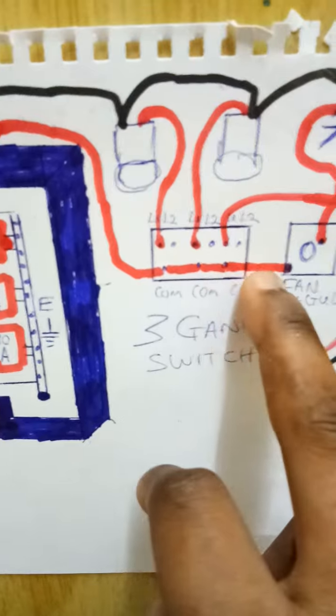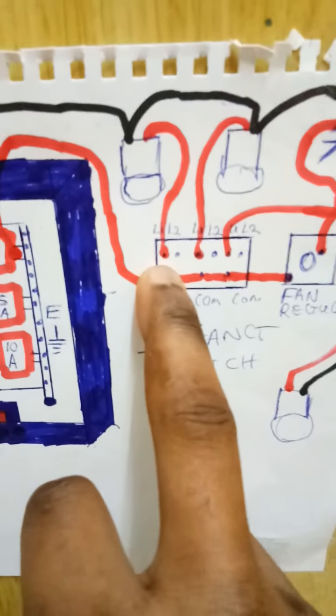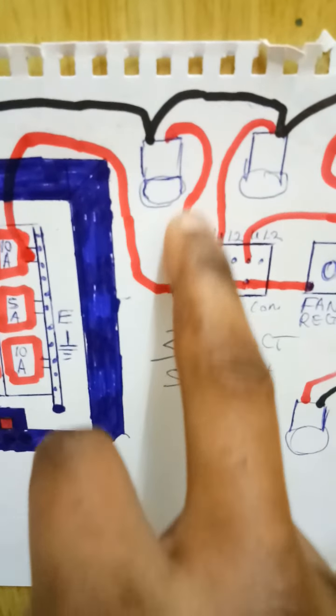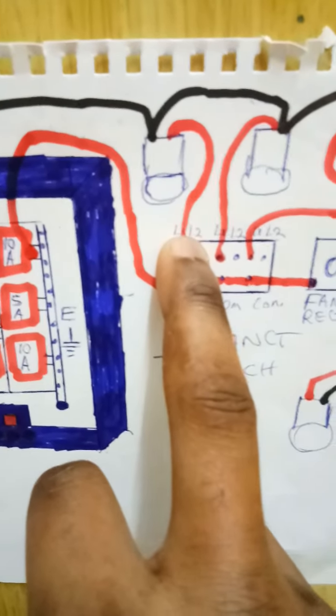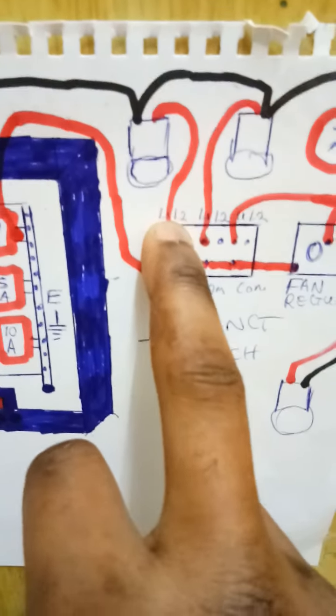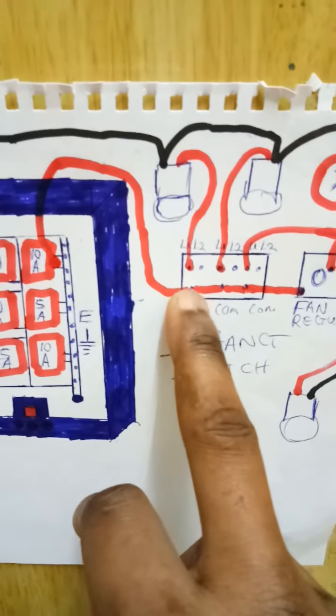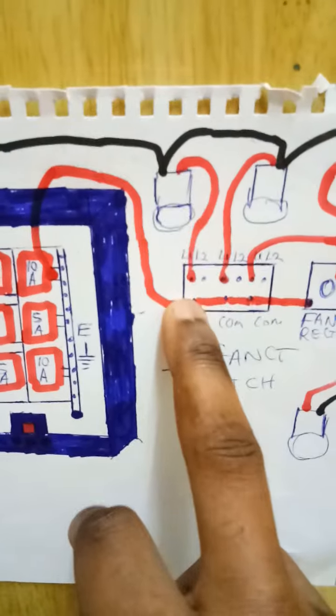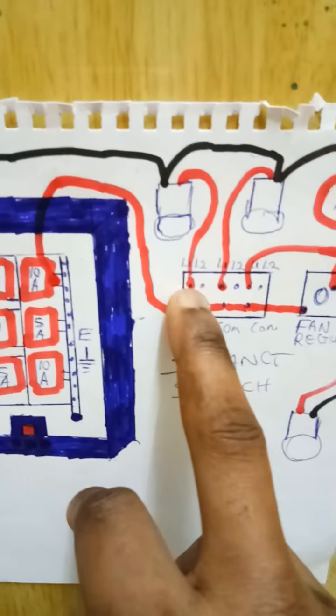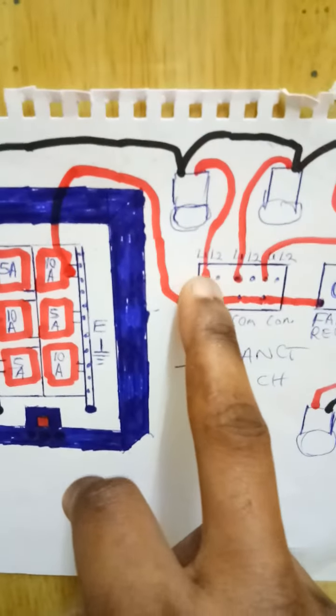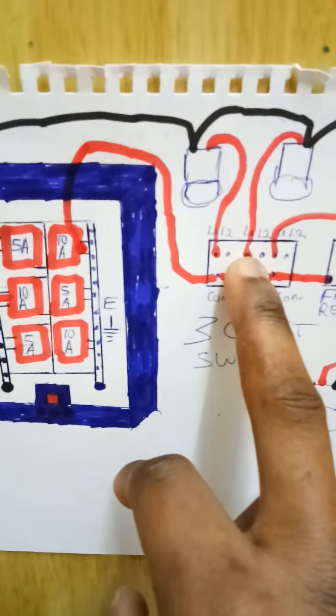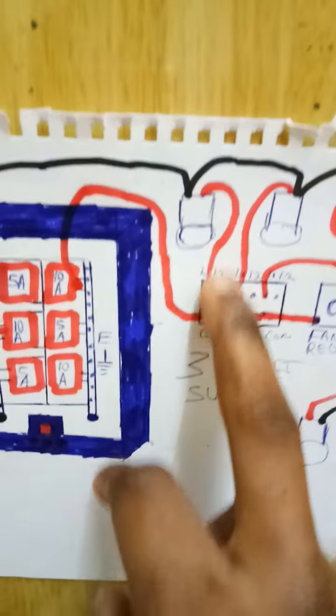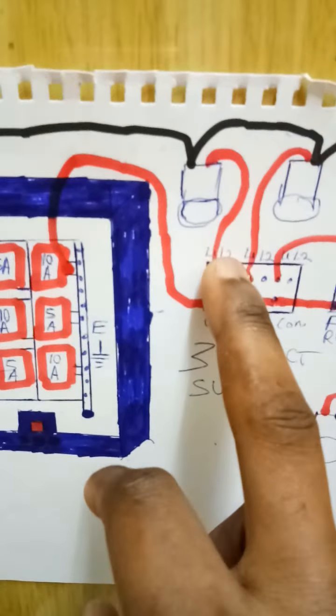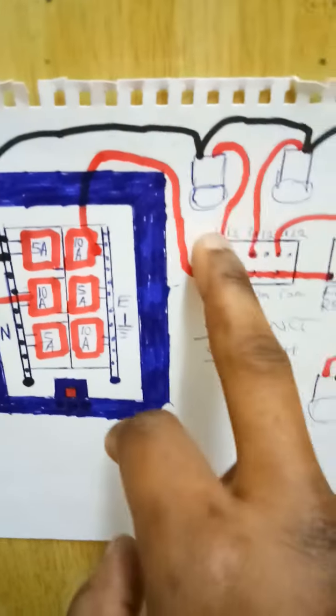That's what you should know as a beginner. The live wire from the circuit breakers will always go to the common of the switches, whereas to the lighting points you take from either L1 or L2, so that when you turn on the switch, the lighting points will turn on. When you turn off the switch, the lighting points will turn off. This is how make and break is achieved in a conduit system. What I'm telling you is what happens inside a conduit pipe. If you can imagine it and understand it in your imagination, you can manipulate it anyhow you want. But this is for you to understand how it goes.